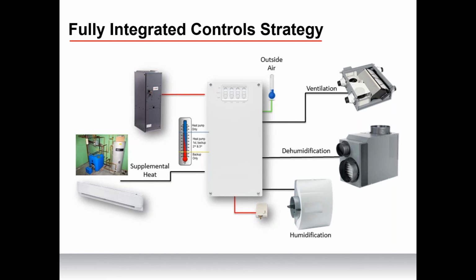We want to utilize that air source heat pump as much as we possibly can. Let's get that efficiency out of it. I want to wring every bit of COP, every bit of efficiency, out of that air source heat pump before I need to integrate electric backup heat, specifically electric, because electric resistance, as we all know, is 100% efficient, it just costs a boatload to operate, right? So if electric resistance is our backup source, I want to mitigate that and limit the usage of that as much as possible, completely if I can. But if I'm in a climate that absolutely needs it, let's make sure we get all of our efficiency out of that air source heat pump before we have to engage that electric resistance.